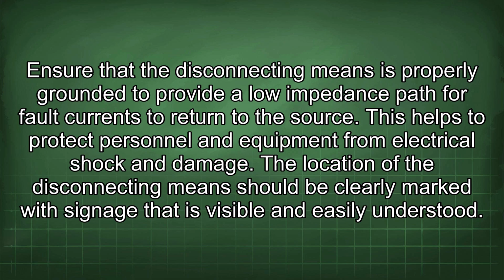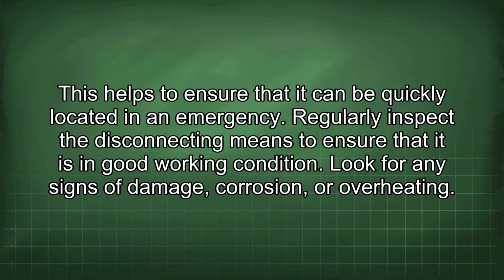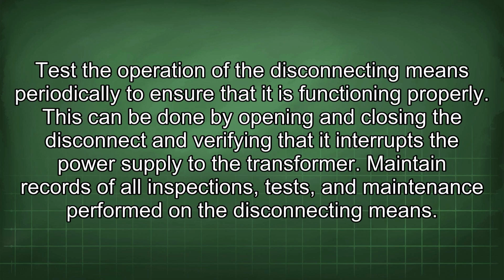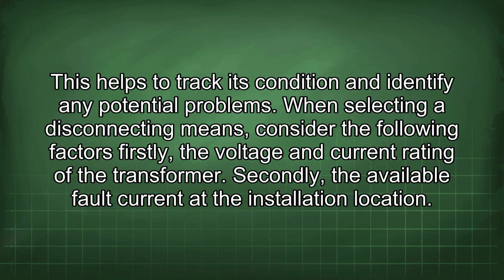The location of the disconnecting means should be clearly marked with signage that is visible and easily understood. This helps to ensure that it can be quickly located in an emergency. Regularly inspect the disconnecting means to ensure that it is in good working condition. Look for any signs of damage, corrosion, or overheating. Test the operation of the disconnecting means periodically to ensure that it is functioning properly. This can be done by opening and closing the disconnect and verifying that it interrupts the power supply to the transformer. Maintain records of all inspections, tests, and maintenance performed on the disconnecting means. This helps to track its condition and identify any potential problems.